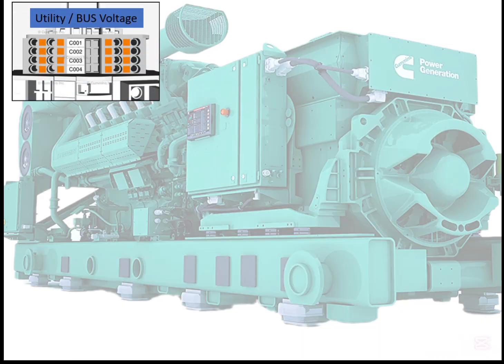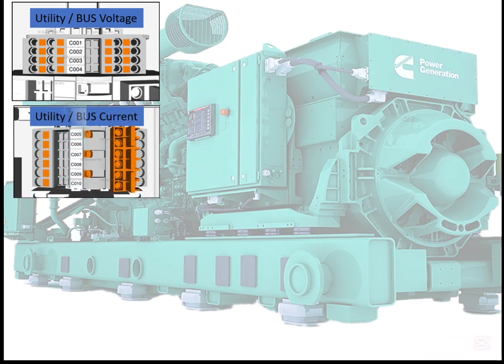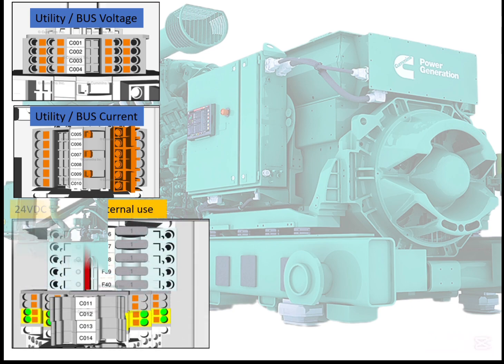So let's look at the physical picture of the connectors. This is the first we discuss: the utility bus voltage labeled C001 to C004. This is the utility bus current or differential clamp CTs, labeled C005 to C010. These are the 24-volt external use supply fuses and negative return supplies.